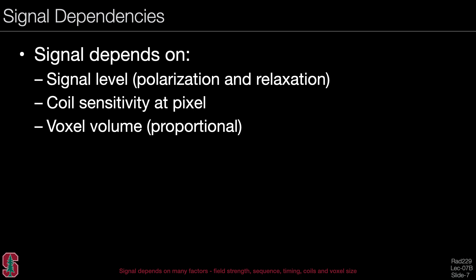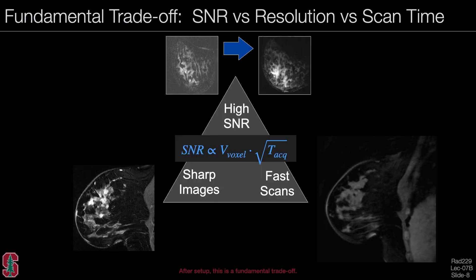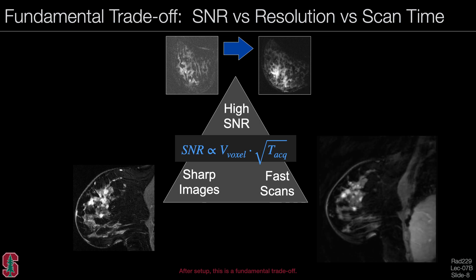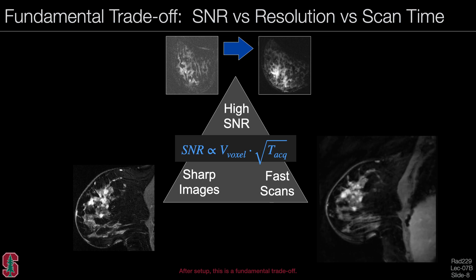Now let's look at signal dependencies. The signal depends on the signal level due to polarization and relaxation, the coil sensitivity at that pixel, and the voxel volume — it is in fact proportional to the voxel volume. There is a fundamental trade-off of SNR versus resolution versus scan time. The SNR is proportional to the voxel volume and the square root of the total A-to-D time. We are always competing between high SNR, sharp high-resolution images, and fast scans — this is a fundamental trade-off in MRI.